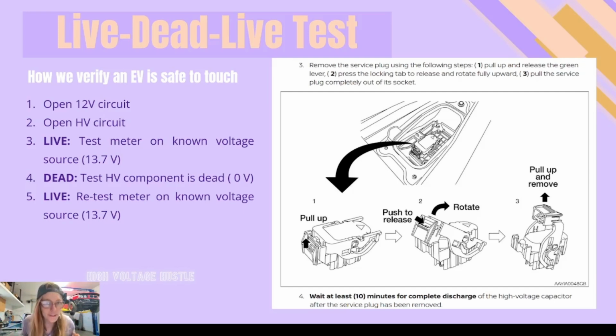Why do we do that? Because you could have been getting 0 volts during the dead test because you blew the fuse in your meter, and you actually have live voltage there. So you always go back and make sure your meter is still working properly so you can trust that those 0 volt measurements were truly 0.